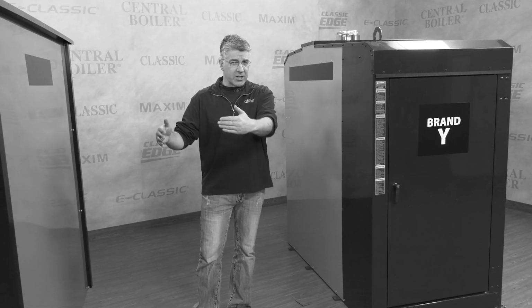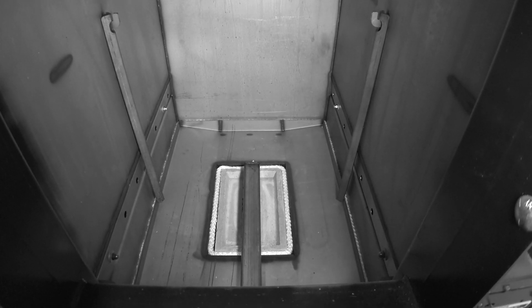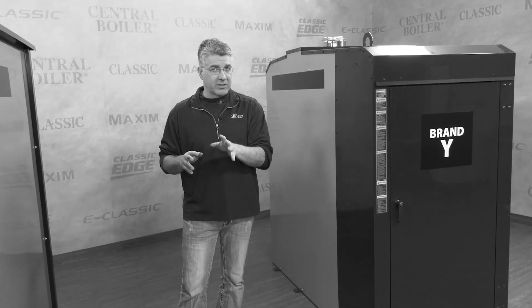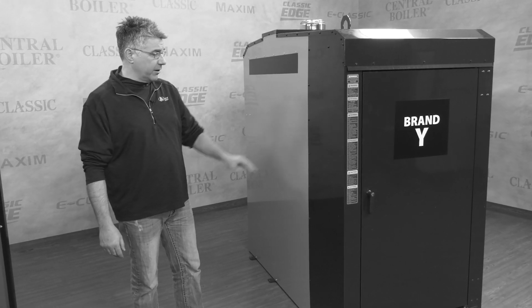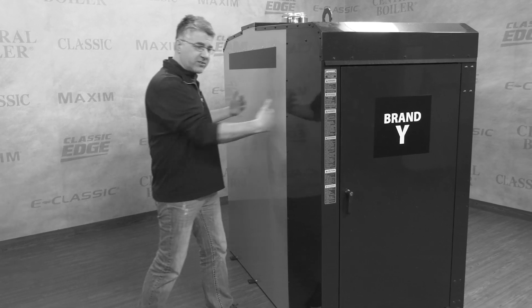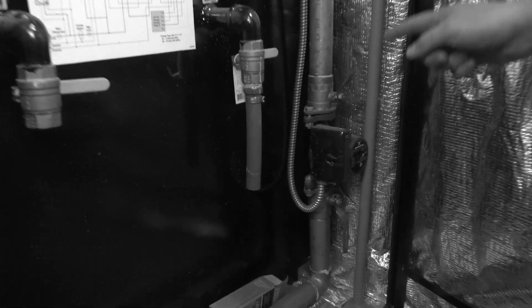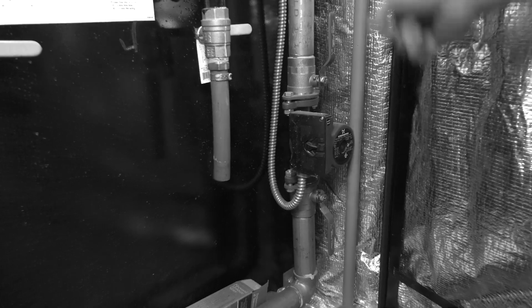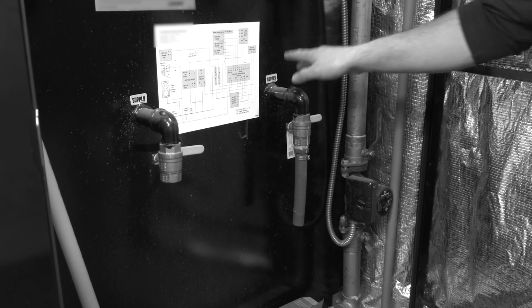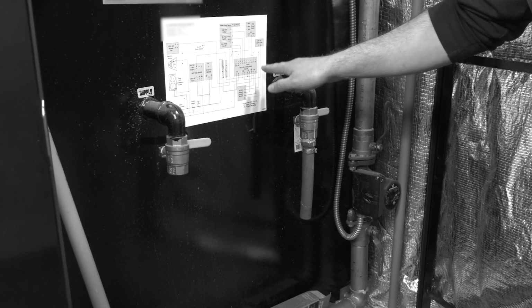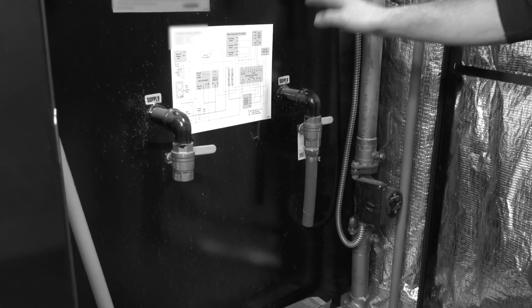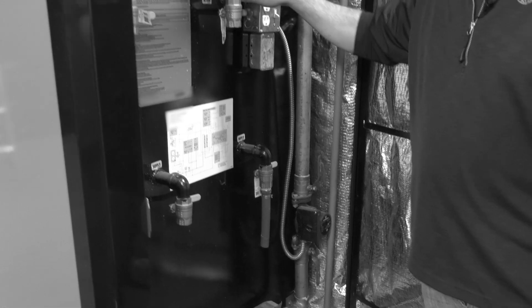2 things I want to talk about: air channels and wraparound pumps. On the Classic Edge, the air channels are removable, so if somebody plugs something up, you could easily take that air channel off and get to it. Remember, every nook and cranny is accessible on the Classic Edge. Now, on Brand Y over here, if you plug up the side air channels, the whole side of the furnace has to come off. Okay, over here, both models, X and Y, have wraparound pumps, which require a lot more electricity. It runs constantly circulating the water. The reason they're doing this is because they're pulling the hot water supply off the bottom of the firebox, or close to the bottom. Why not pull the hot water off the top, like we do? It makes sense. Your water heater does it that way.